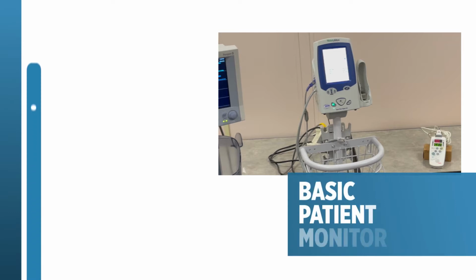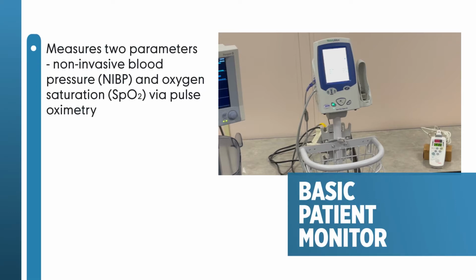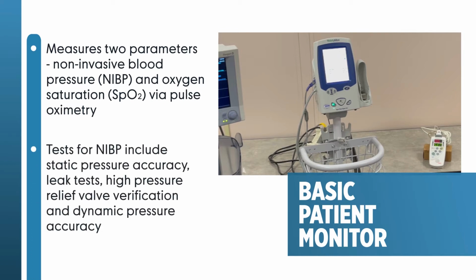Basic patient monitors measure two parameters: non-invasive blood pressure and blood oxygen saturation via pulse oximetry. Tests for non-invasive blood pressure include static pressure accuracy, leak tests, high-pressure relief valve verification, and, if specialized test equipment is available, dynamic pressure accuracy. The device may have to be put in service mode to make these measurements.